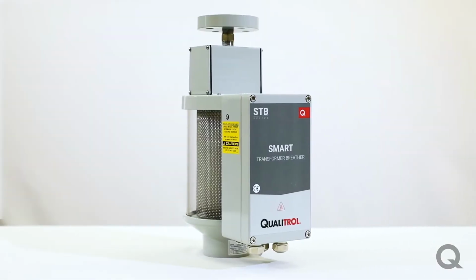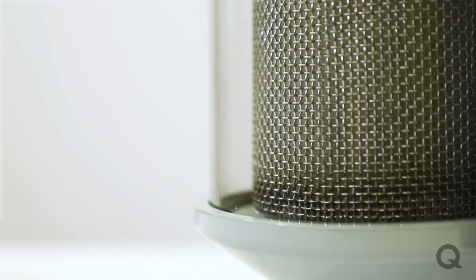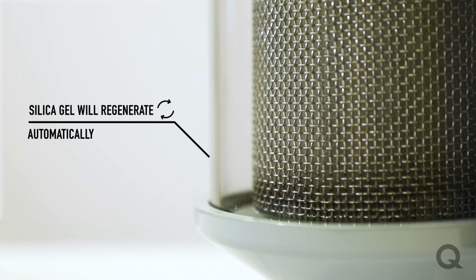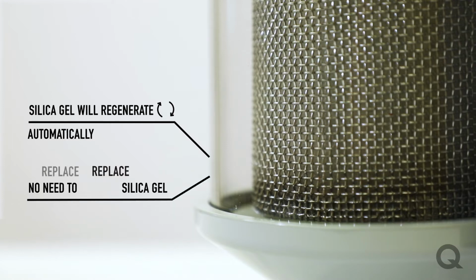Smart breathers are very similar to a traditional breather in the sense that they both use a silica gel desiccant to dry the atmospheric air entering the transformer. But instead of needing to replace the desiccant when saturated, the breather will regenerate the silica gel so that it can keep absorbing the moisture. And this is a big point of a smart breather because the breather can do the regeneration of the silica, and that eliminates the need to go to the field to replace that silica gel, reducing maintenance costs.